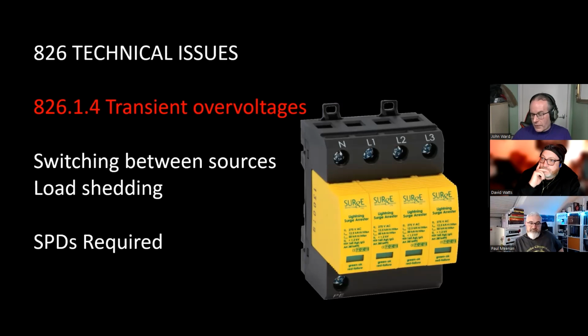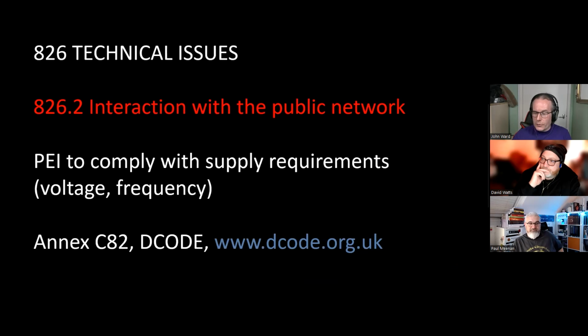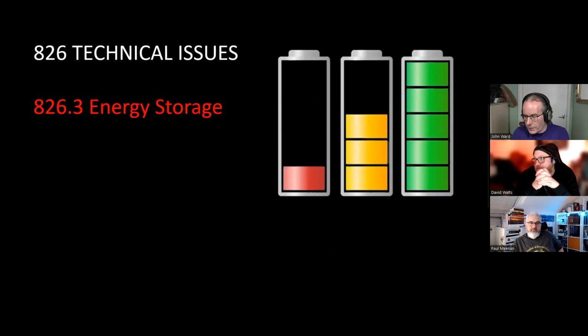Transient overvoltage. So in other words, it's surge protection again. You're going to be switching between different sources. You're going to be changing loads on and off all the time. So surge protection is required. There's no question about that whatsoever. And in terms of connecting to the public network, you need to comply with the supply requirements, such as the voltage and the frequency. So that comes down to more of equipment standards. Again, there is an annex in BS 7671. And there's also a website, which is dcode.org.uk, which covers quite a lot of that, and that's freely available.